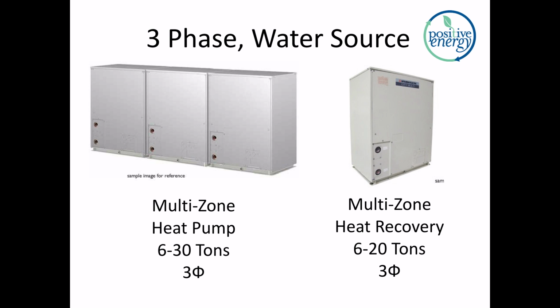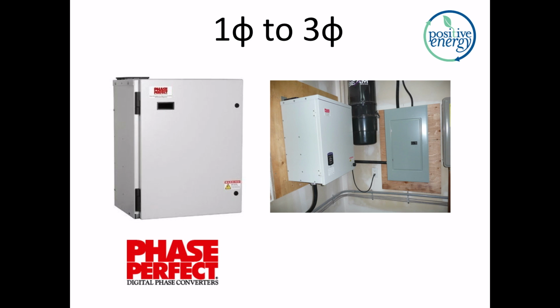So same applications, same considerations go into these multi-zone heat pump or heat recovery systems that are water source. Again, these are three-phase now. And the capacities go from what could be a big residential application to as big as you need. There are many applications now where we are looking at the possibility of converting single-phase power in a residential system or a light commercial context to three-phase power so that we could run one of those three-phase systems. There are known applications where a phase converter has been used to convert, in that picture there, I have a single-phase panel and create three-phase output to run one of these. There is some lack of clarity on the side of the manufacturers as to whether that's okay with them. So consult with your manufacturer, consult with your application specialist to make sure that they're good with that.